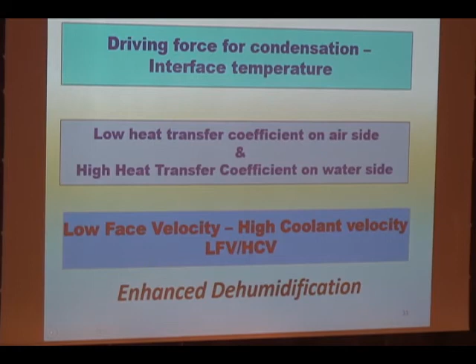Heat pipe is a strategy where we just wrap it around a cooling coil. This is called the pre-cooling section. This is the reheating section. There's a refrigerant inside that is in liquid state. It picks up the heat and then it goes over, as a vapor, onto this side here on the reheater side. It passes its heat to the cooled and dehumidified air, becomes liquid, comes back, and the cycle continues. As long as the coil is in operation, the heat pipe works.